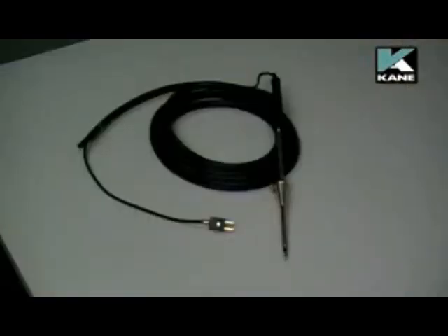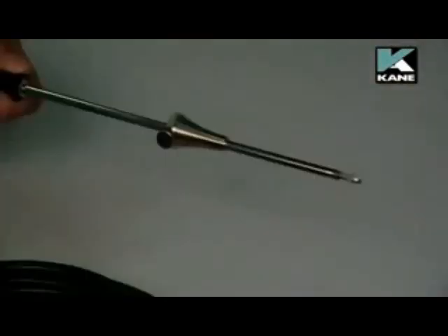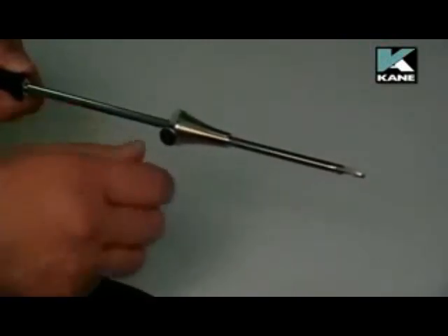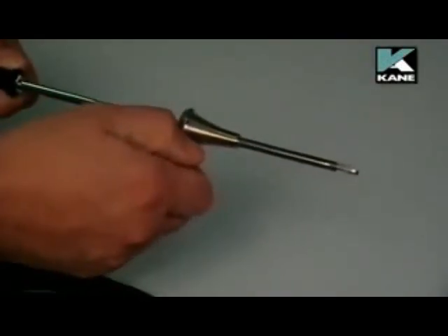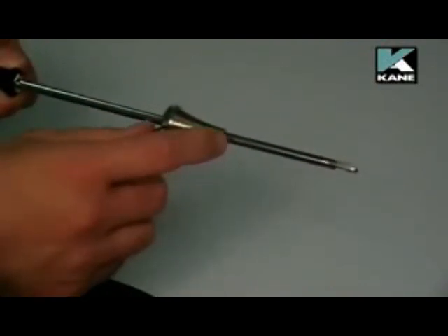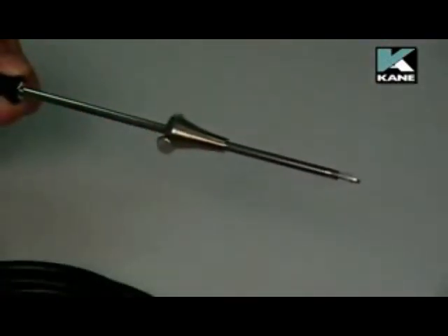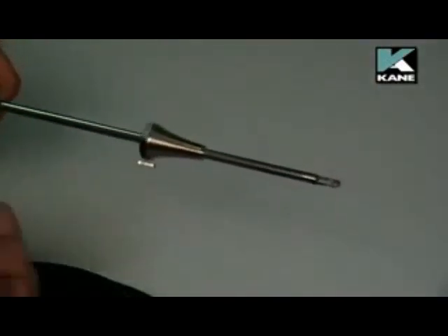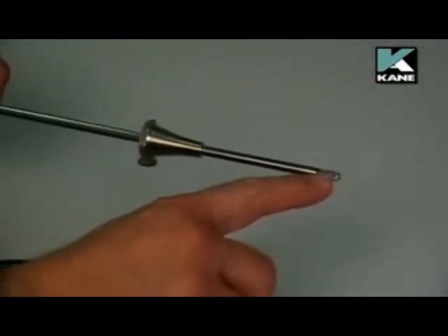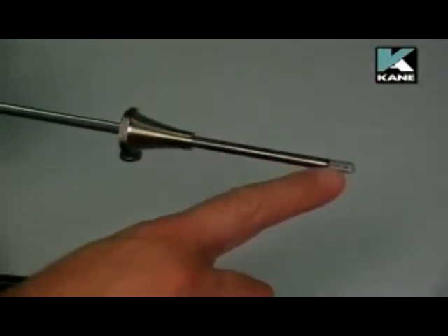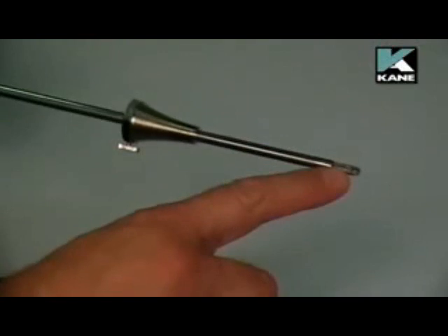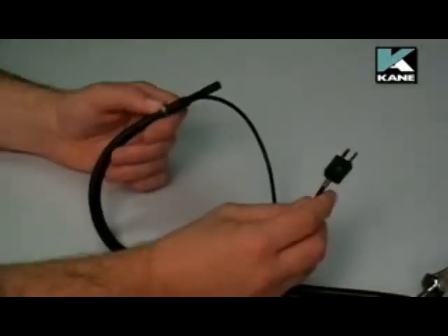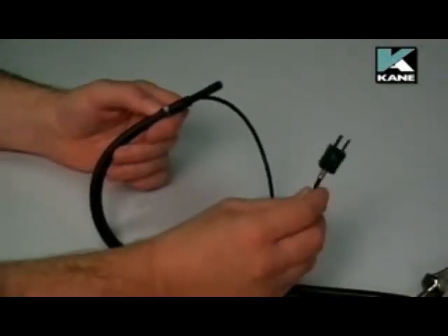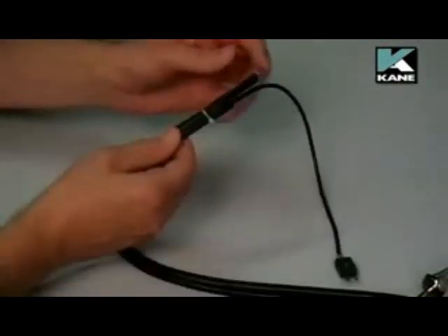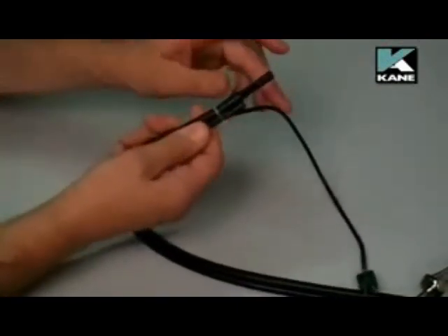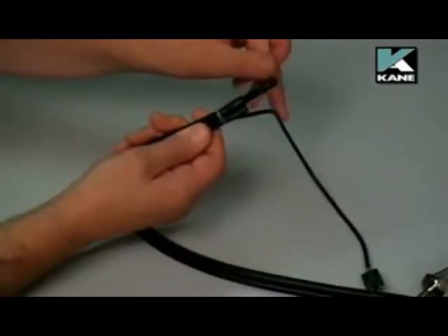This is the standard flue probe. On the shaft of the flue probe you've got this adjustment cone, so you can actually gauge how far you put the probe into the flue of the boiler. On the tip of the probe you have a thermocouple, this wire, so that's actually going to measure flue temperature. The cable from the thermocouple runs down the side of the hose to this plug. The actual hose itself has a connector, a black connector with 2 O-ring seals.